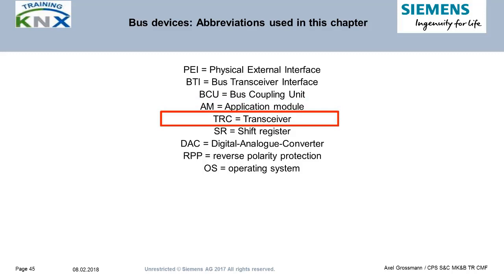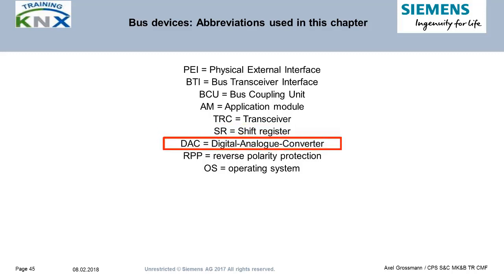TRC is the part of the BCU that deals with transmitting and receiving bus telegrams. Today it is only an ASIC; in the past it was a small electronic board inside a BCU. SR stands for Shift Register — in some applications, data between the AM and BCU are exchanged by means of a shift register. DAC stands for Digital Analog Converter.